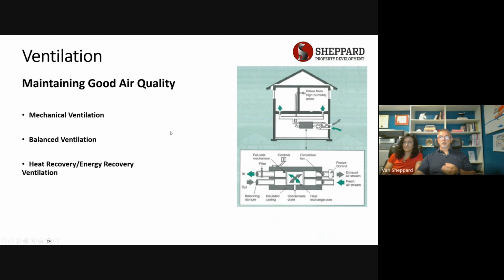And you're going to do that pretty much constantly at a fairly low rate. There's calculations for how many air changes you should have per hour in a building, and then these fans that you see here, they're usually pretty small. They don't move a lot of air. It's low energy and quite efficient, and it's making enough air changes so that your indoor air quality is very high, but it's in a controlled environment.